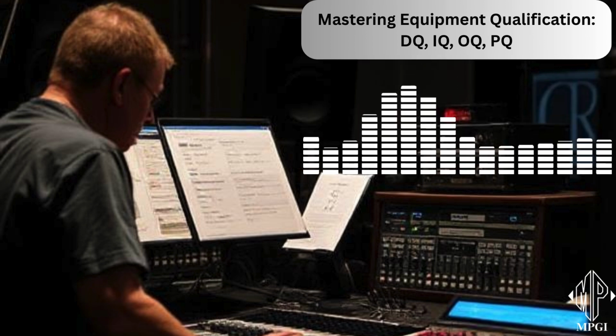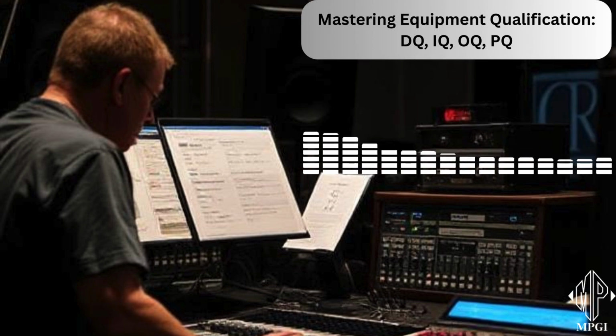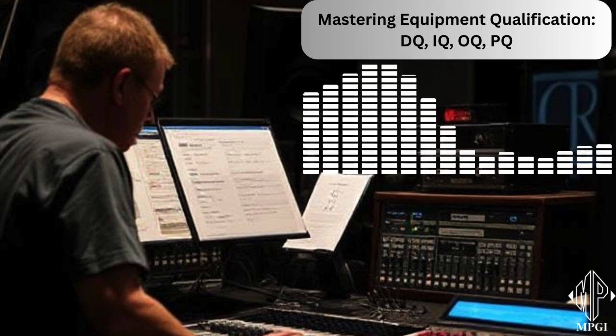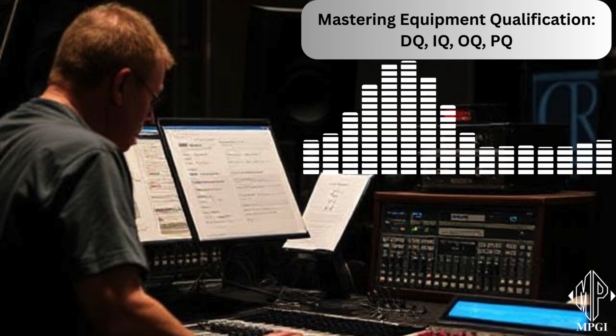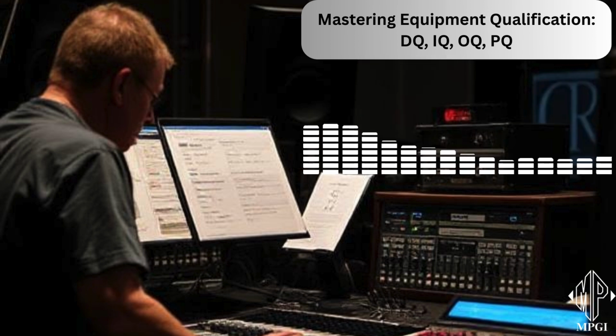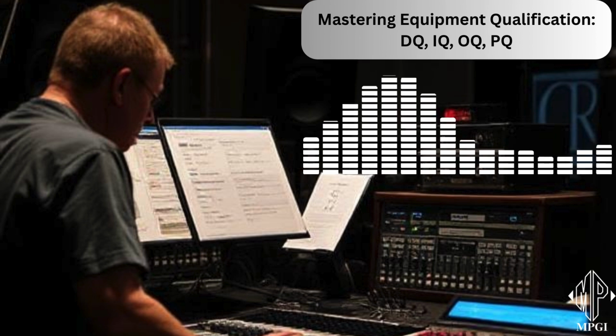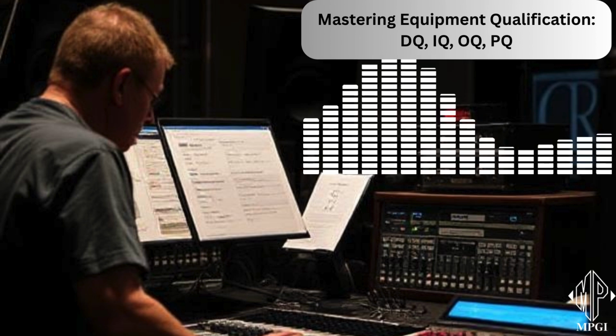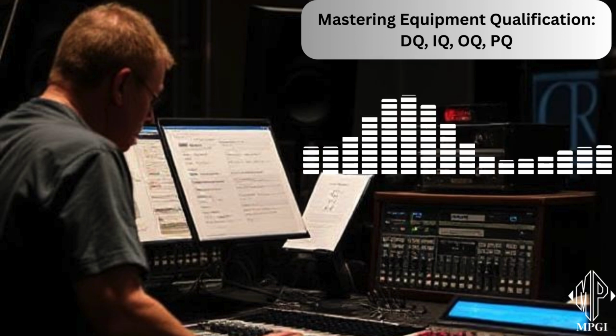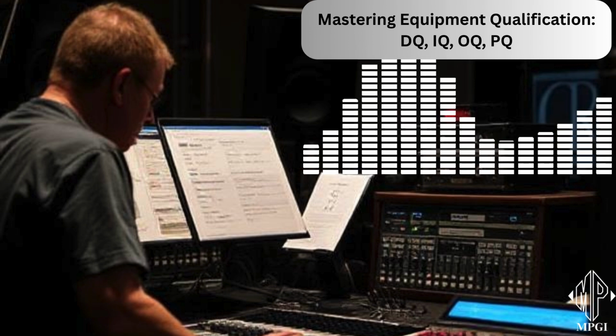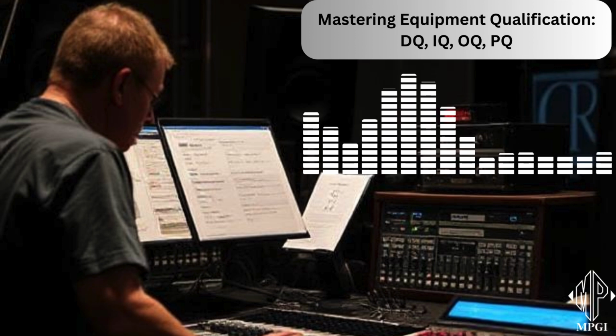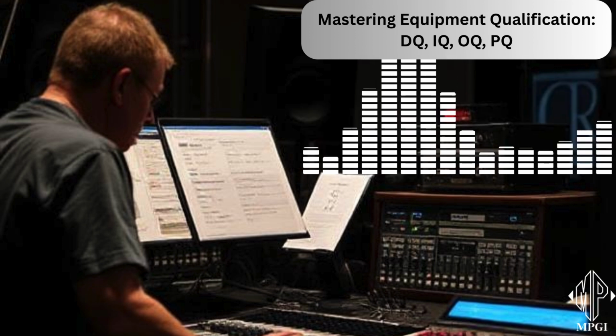Right. You also mentioned periodic requalification. What does that involve? Periodic requalification is basically checking up on the equipment at set intervals to make sure it's still operating within specs and meeting all the requirements. So it's like a checkup for the equipment. Exactly. And you might also need requalification after major maintenance, modifications, or upgrades. The frequency and depth of requalification should always be based on a risk assessment. So how often you check up on it depends on how critical the equipment is and how likely it is to have problems.